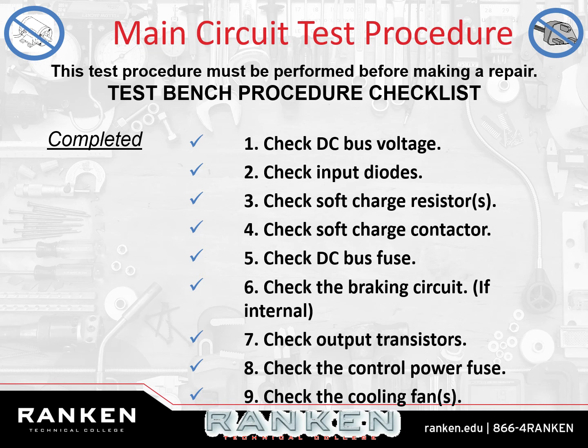And the problem is most of the time you have to take these drives completely apart to access those diodes. To check the resistors, you have to too. To check the charging contacts, you have to too. Most of these are going to be on the bench, and you have to take the drive completely apart. Therein lies the problem. Like I said, to take these things completely apart and to try to troubleshoot it down to a component level takes forever.